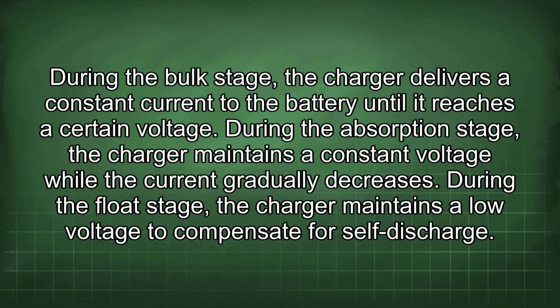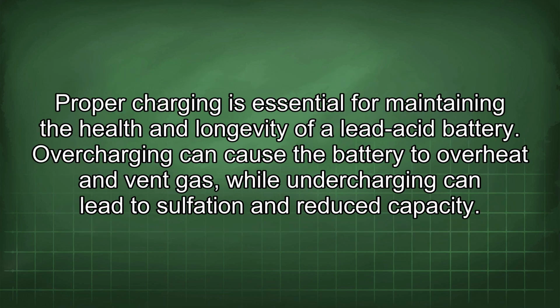During the absorption stage, the charger maintains a constant voltage while the current gradually decreases. During the float stage, the charger maintains a low voltage to compensate for self-discharge. Proper charging is essential for maintaining the health and longevity of a lead-acid battery. Overcharging can cause the battery to overheat and vent gas, while undercharging can lead to sulfation and reduced capacity.